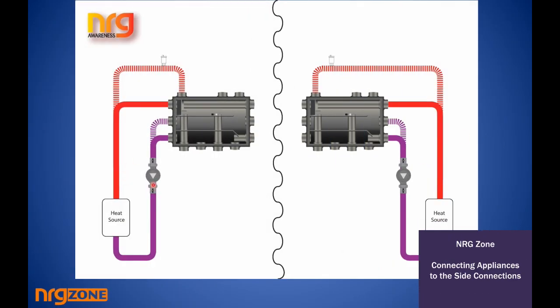So now we're looking at where could you connect zones to a system, or heat appliances to a system. So you could take your return water from the coldest chamber, the return chamber. You could go to the bypass chamber because again, look, you've got a big opening here. So yes, you could take your return here down into your pump, around through your heat source and up. You can go directly into the top chamber here, but if you go up over and get rid of the air, you're also in the exact same place because that and that arrive at exactly the same place within milliseconds of each other.